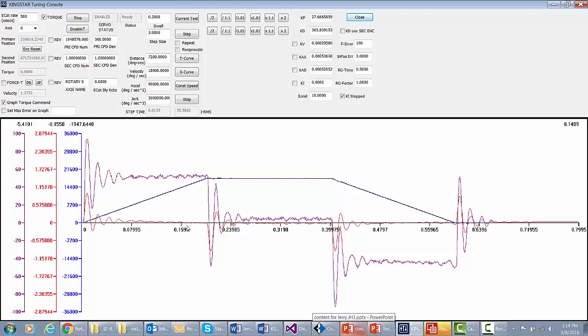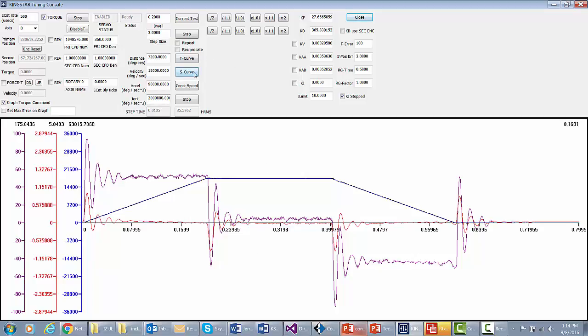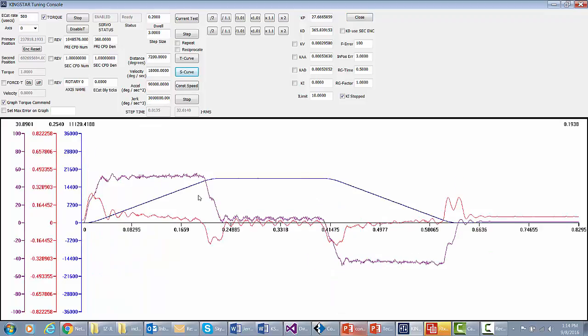Now most of the trip, you're down in the noise, but right here, the error is minus 0.9 degrees. So we'd like to do a little better, so we're going to do an S-curve. Instead of having these sharp edges, we're going to do an S-curve, and here you'll see that we've rounded off these corners. Our error has gotten significantly better.